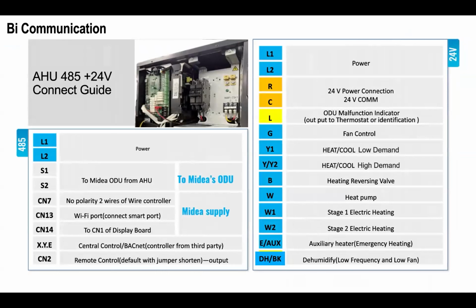All right, wire connections in the AHU. So L1 and L2 are self-explanatory. That's your power coming in. S1 and S2, which are on the display board, is the wiring that goes from your outdoor unit, or goes to the outdoor unit from the AHU.